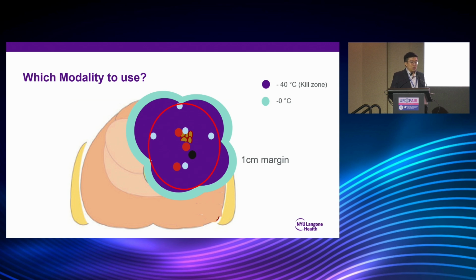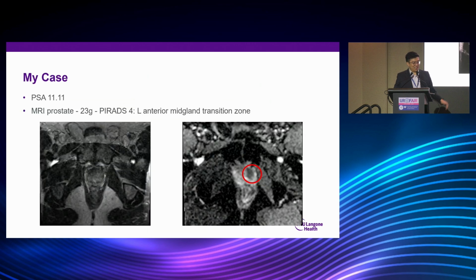So usually when you do cryoablation, you have a kill zone and a freezing zone, because tissue usually freezes at about minus 2 or minus 3. The freezing point of water is 0 degrees Celsius, but tissue usually needs a little bit more. So when you look at the ultrasound probe, you see ice. It doesn't mean that's the kill zone. So you have to make sure we map out the kill zone. And in that lesion that Jack gave us, easy. After this, everything is dead.